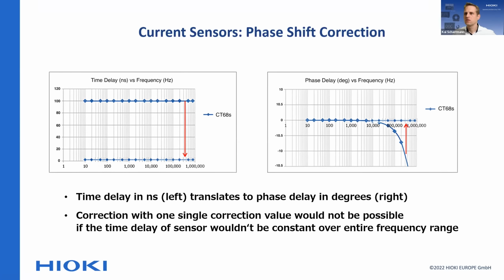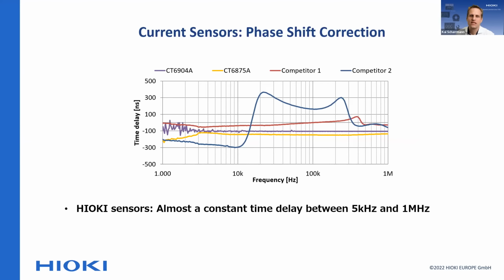So the power analyzer knows which sensor is being used, and it knows the error of that sensor, this constant phase delay, and that allows us to make that correction with just one value. That's why I said Hioki has this constant time delay. If you compare this again with the competition, it's the same sensors that we used before, both very popular, and they are specified to be used for this kind of measurement. If you look at the phase delay, you can see that this is not a constant time delay, and that has the effect that one single value is not going to be suitable to make any kind of correction. So phase correction as we do it will not work with that.